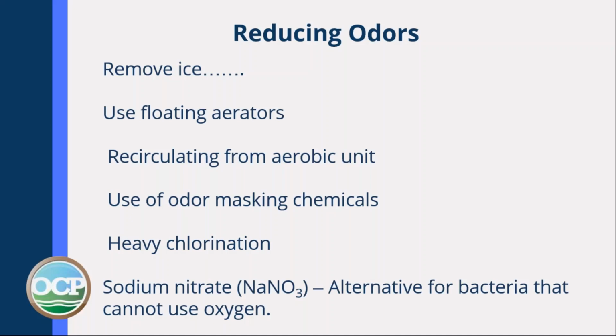You can use heavy chlorination, but then you must make sure you either dechlorinate or have sufficient detention to allow the chlorine to break down naturally. Sodium nitrate, NaNO3, is an alternative for bacteria that cannot use oxygen.